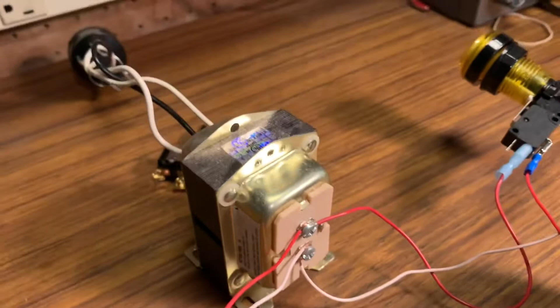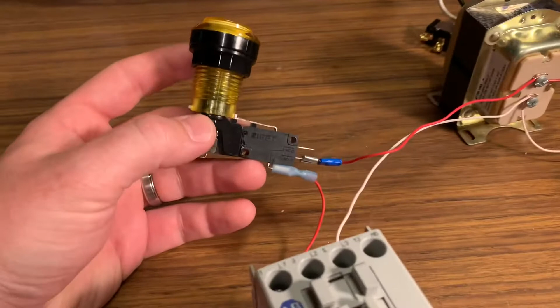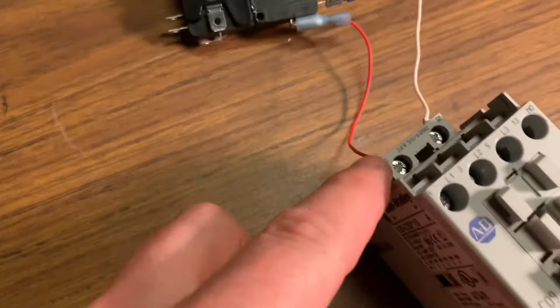24 volts AC is what's needed to energize these coils to pull in the relay. 24 volts comes out on the red, and we're gonna have that interrupted by a micro switch here. When you throw this switch, it will complete the circuit and continue sending the power to one side of the contactor. The other side of the contactor is your common, and that'll get wired up to the common side of the transformer.